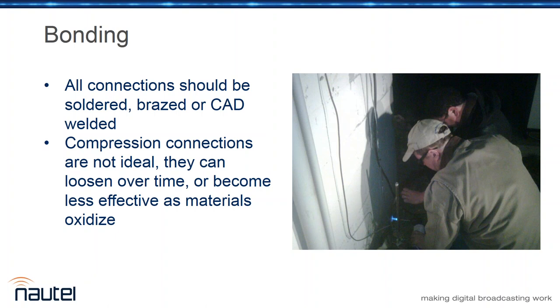As I said before, everything should be exothermically bonded. Electromechanical connections, whether soldered, brazed, CAD welded, less important, but the idea is to displace as much oxygen as possible and give as solid a connection as we can. Especially if you're running a stranded wire ground, like a 1/4-inch copper cable made out of stranded wire, those will, in the usual ground rod clamps, come loose over a period of time. So they need to be tightened regularly. You need to keep the oxidation off them.